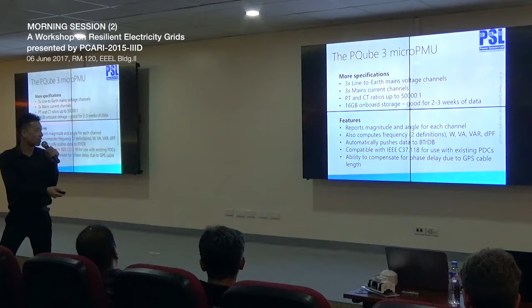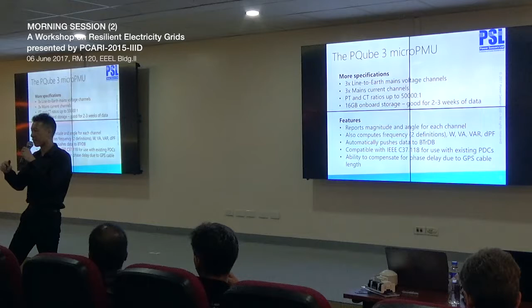And it's frozen again. But basically, our written specification is 0.05% of reading and percent full scale, which is how you're supposed to specify your accuracy for voltage and current.